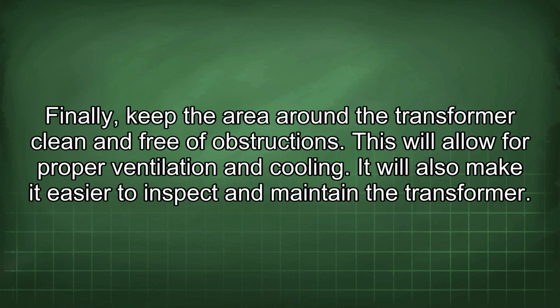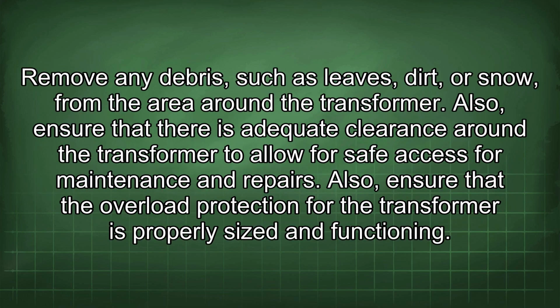Finally, keep the area around the transformer clean and free of obstructions. This will allow for proper ventilation and cooling. It will also make it easier to inspect and maintain the transformer. Remove any debris, such as leaves, dirt, or snow, from the area around the transformer. Also, ensure that there is adequate clearance around the transformer to allow for safe access for maintenance and repairs.